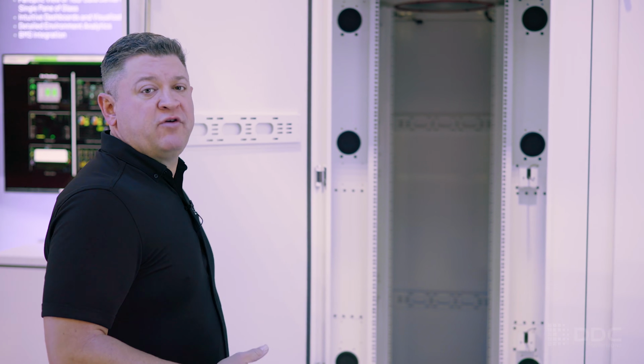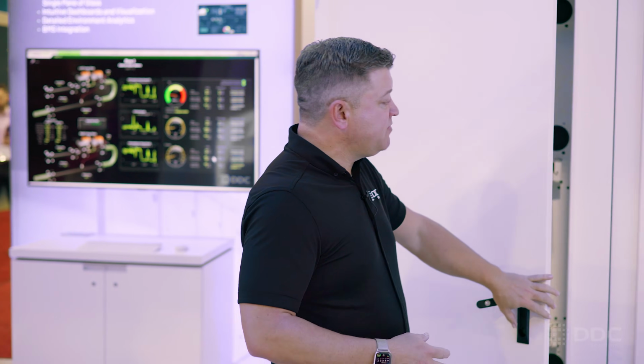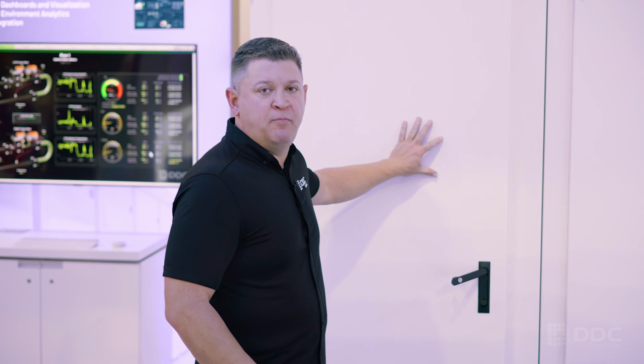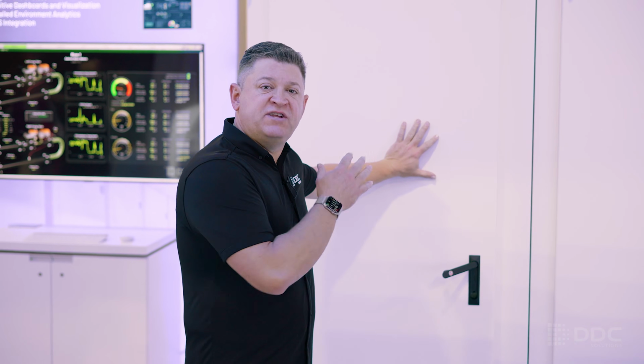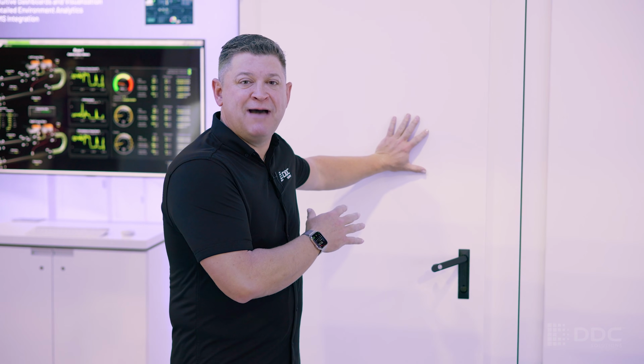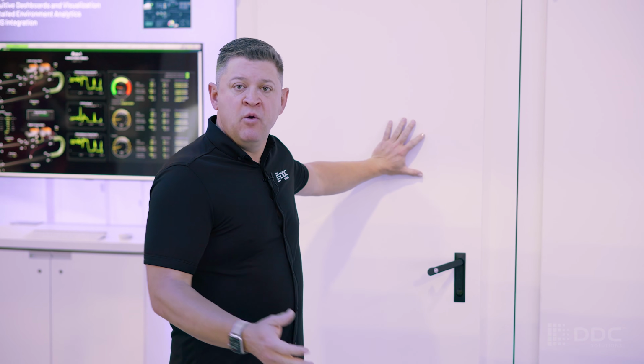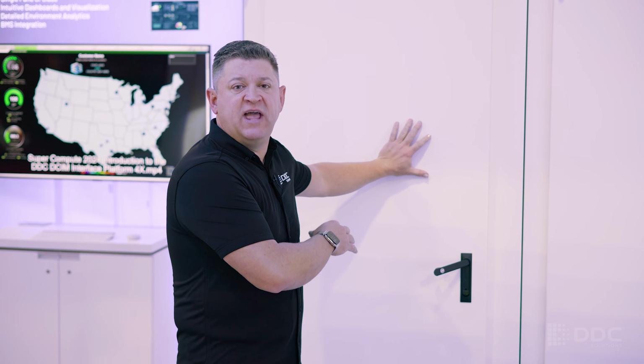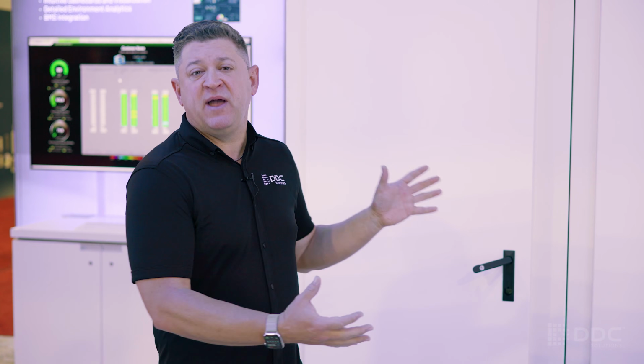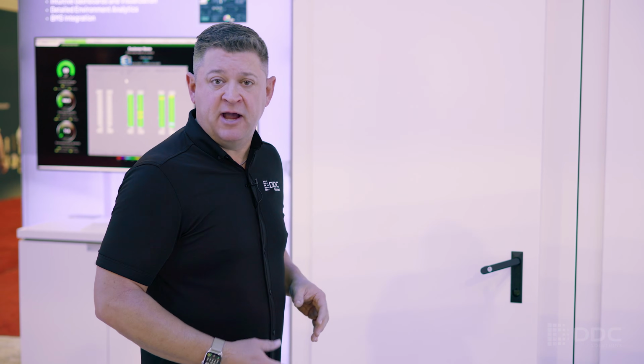That protection also completely helps with sound attenuation. Today's advanced GPU clusters and AI deployments are louder than they've ever been before, and because of the completely sealed model of the DDC cabinet, we now are attenuating most of that sound inside the cabinet. Same goes for heat transfer. With over 100 kilowatts of activity happening in a cabinet, the DDC cabinets are specifically designed to reduce heat attenuation out into the data center space. So you end up with a quieter, cooler, and more efficient data center environment simply because of the ruggedization of the DDC cabinet design.